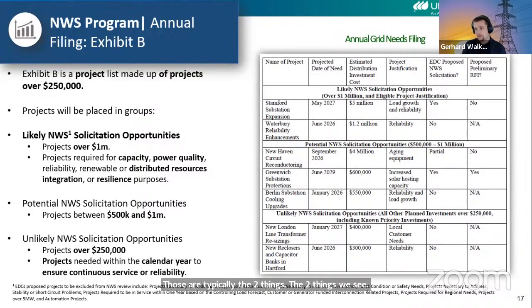And the last item is, from a planning standpoint, non-wires solutions are geared exactly to the need at hand. For example, if you have a half a megawatt capacity deficit, nobody would argue we should deploy a 5 megawatt battery — that's overkill. But that also means that if electrification goes a bit faster than expected, the expected impact of that non-wires solution gets diminished really quickly, even once deployed, because the capacity it grants gets used up faster. Because costs are incremental to capacity, you want to be as close as possible to your need, otherwise it gets too expensive. They leave very little room for additional load growth above and beyond what's projected.